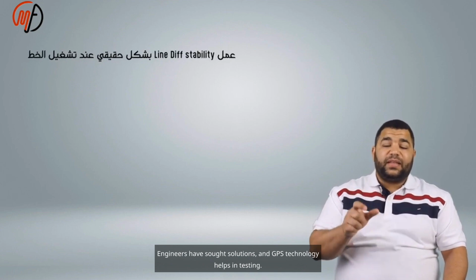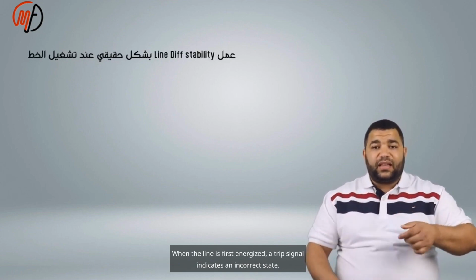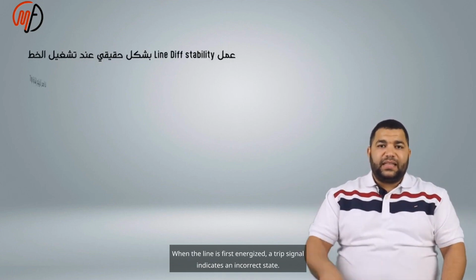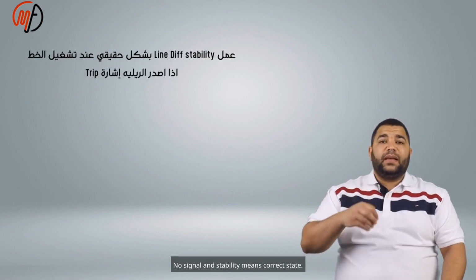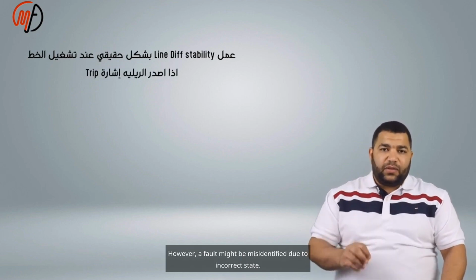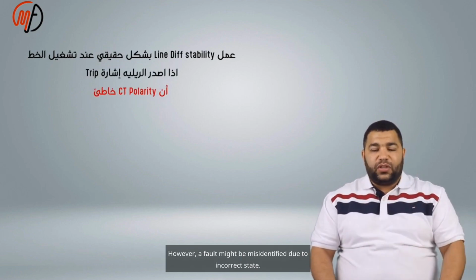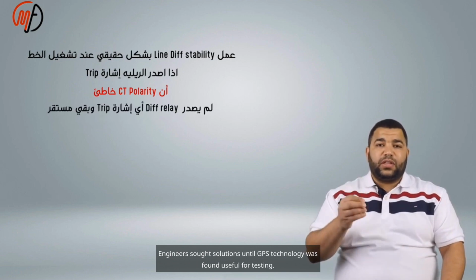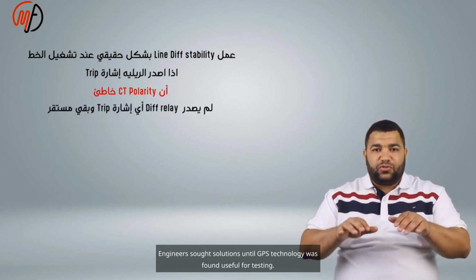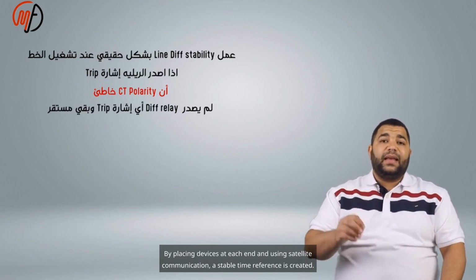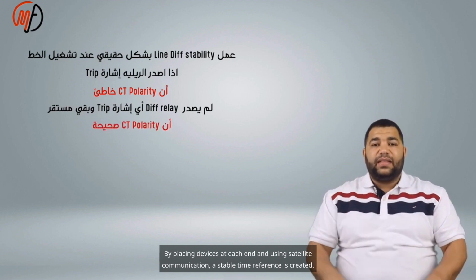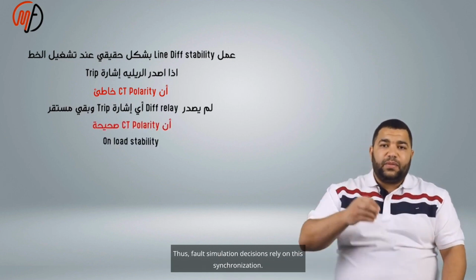Engineers have sought solutions, and GPS technology helps in testing. When the line is first energized, a trip signal indicates an incorrect state, no signal and stability means correct state. However, a fault might be misidentified due to incorrect state. By placing devices at each end and using satellite communication, a stable time reference is created. Thus, fault simulation decisions rely on this synchronization.